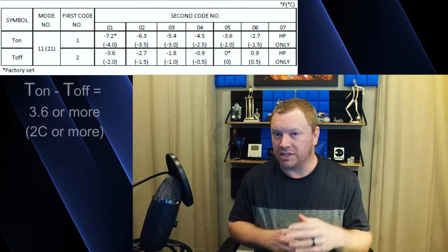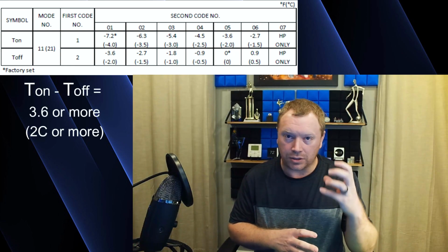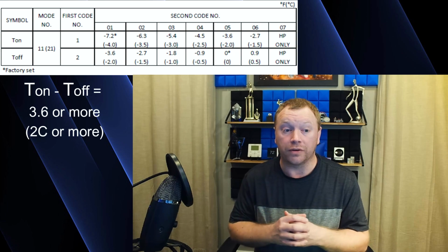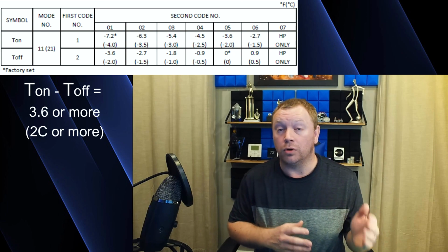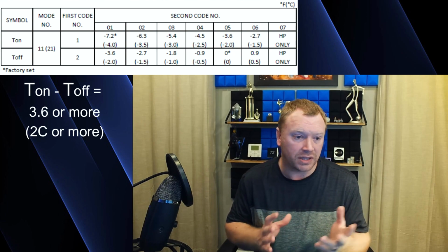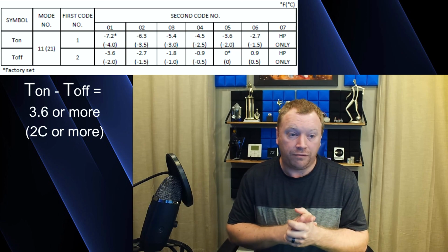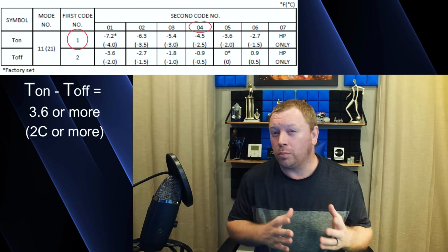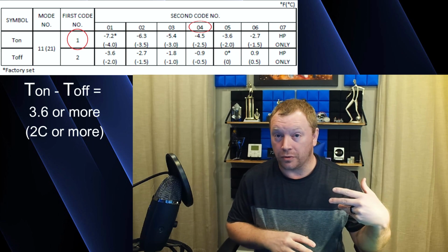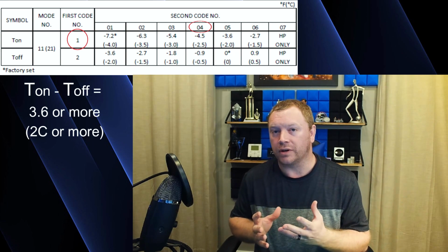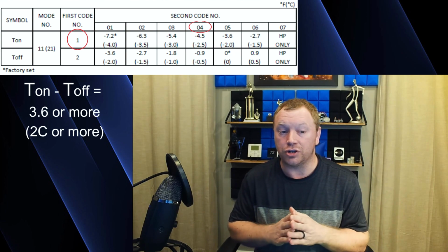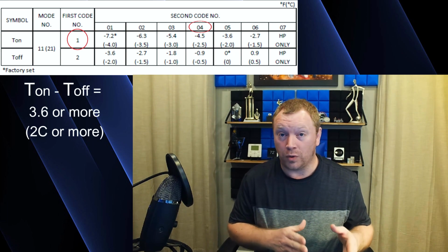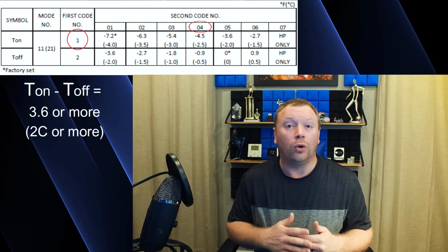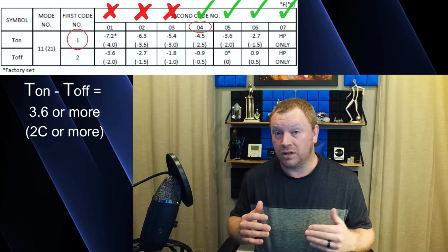Now, just like with your strip heat settings, you do need to make sure that you have at least a 3.6 degree difference between your gas on and your gas off temperature. So if you're going to bump up mode 21, setting 1-01 to let's say 1-04, so that's 4.5 degrees below the set point is where the room temperature has to droop before it kicks on the gas. Just make sure that you have at least mode 21 setting 2-04 or 2-05 or 06 enabled.